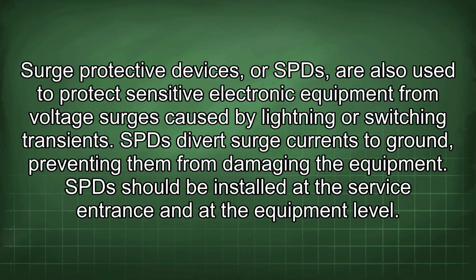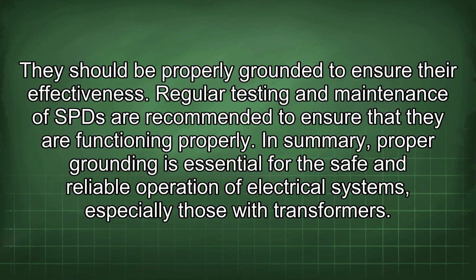Surge protective devices, or SPDs, are also used to protect sensitive electronic equipment from voltage surges caused by lightning or switching transients. SPDs divert surge currents to ground, preventing them from damaging the equipment. SPDs should be installed at the service entrance and at the equipment level. They should be properly grounded to ensure their effectiveness. Regular testing and maintenance of SPDs are recommended to ensure that they're functioning properly.